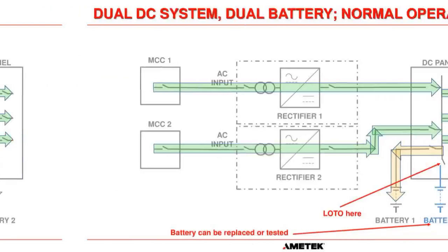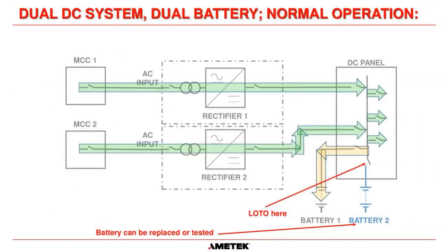Okay. And if you want to replace a battery, my apologies, you can do exactly the same. All you need to do is open this disconnect, and you can do a capacity test on this battery, or you can replace it completely. And both chargers will supply power to the loads and keep the other battery charged. Easy as can be. Really, really great for maintenance. You don't have to take an outage on your load circuits to do work on this system.